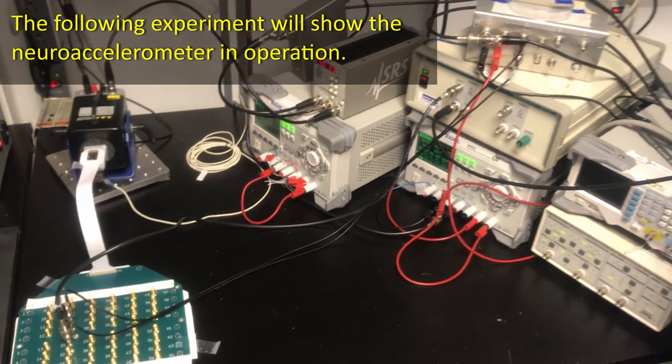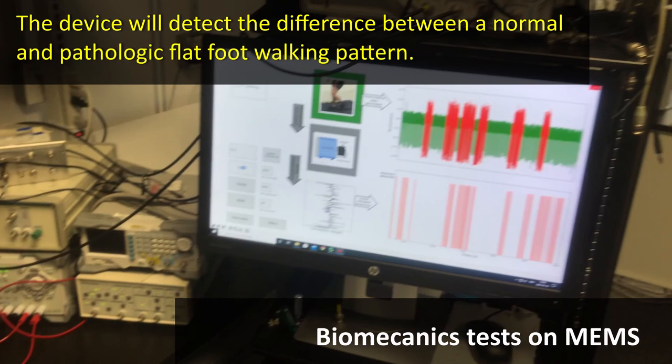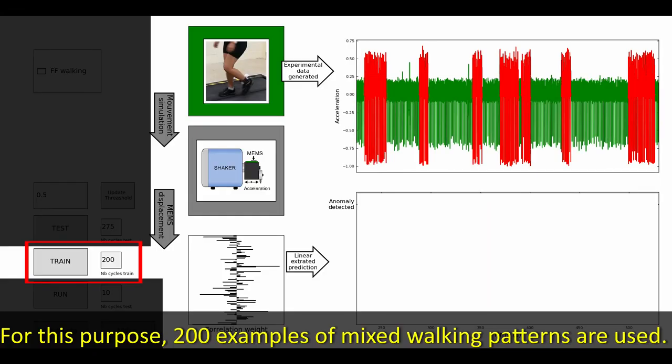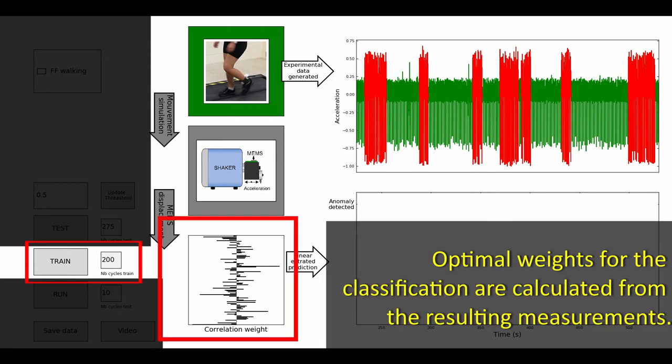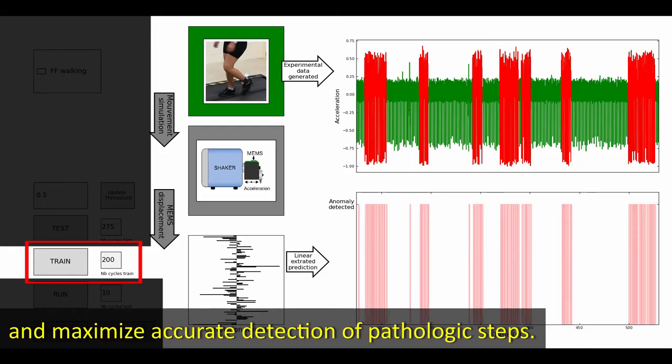The following experiment will show the neuroaccelerometer in operation. The device will detect the difference between a normal and a pathologic flat-foot walking pattern. Since it is a neuroaccelerometer, the device first needs to be trained. For this purpose, 200 examples of mixed walking patterns are used. Optimal weights for the classification are calculated from the resulting measurements. A decision threshold is chosen to allow classification and maximize accurate detection of pathologic steps.